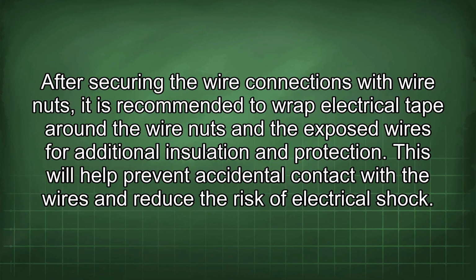After securing the wire connections with wire nuts, it is recommended to wrap electrical tape around the wire nuts and the exposed wires for additional insulation and protection. This will help prevent accidental contact with the wires and reduce the risk of electrical shock.